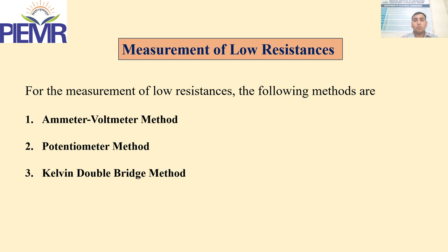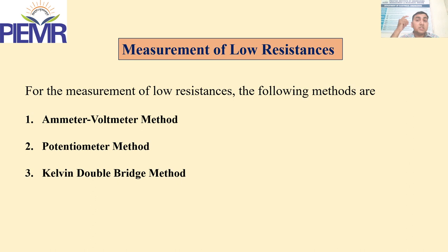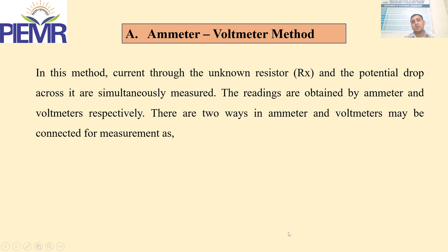Starting with low resistance measurement devices, there are three measurement techniques for resistances below 1 ohm. An important consideration is that if you try to measure low resistance using methods like the Wheatstone bridge or voltmeter-ammeter method, the lead resistance becomes a significant source of error — the connecting leads may have more resistance than the value being measured. Therefore, special methods like the Kelvin double bridge or potentiometer method are used.